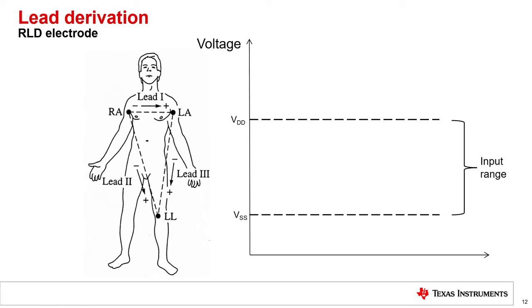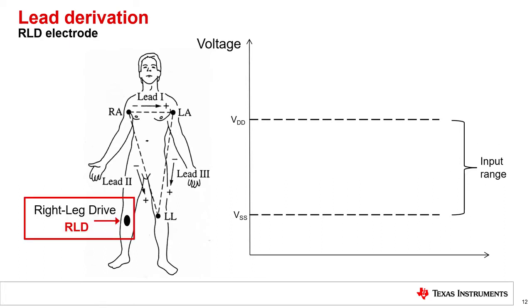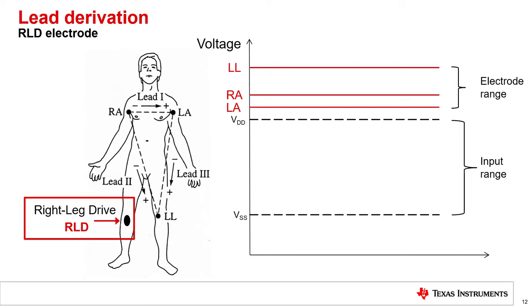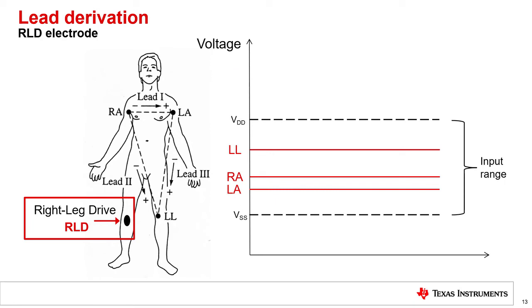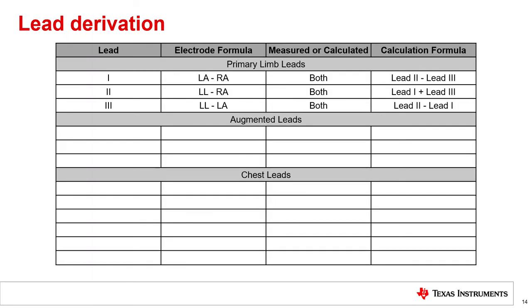In addition to the three primary electrodes, a fourth electrode is commonly used for DC-coupled ECG systems. This electrode is known as the right leg driver, or RLD. The common mode voltage of the human body is floating with respect to the ECG measurement system. Without a way to bias the body, the input signals from the electrodes may not be within the acceptable input range of the ADC. Typically, the voltage on each pin must be within the range of the ADC's power supply, VDD and VSS. The right leg drive electrode drives a voltage to the patient that will cause the DC level of the other electrodes to fall within the supply range of the ECG equipment so they can be measured properly. That covers the first group of ECG leads, the primary limb leads.